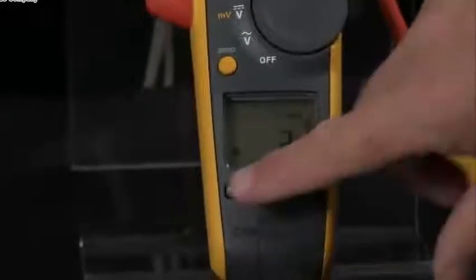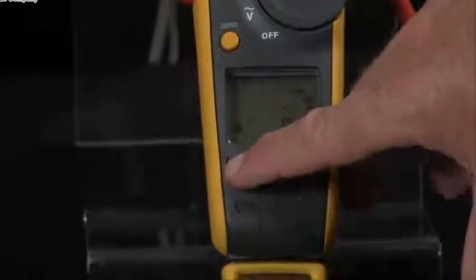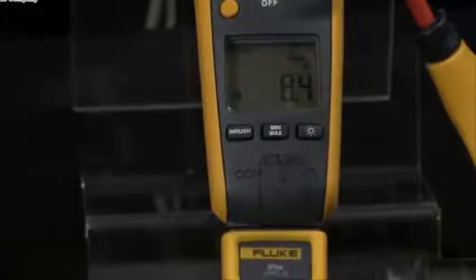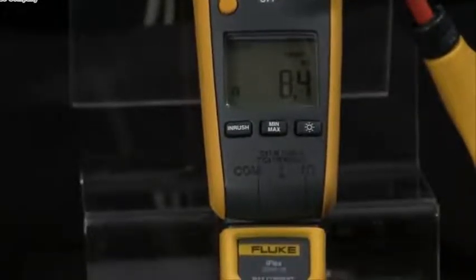To see what the starting or the inrush current is, I press inrush. The meter waits for the motor to start and then it captures my inrush so we can see that we have 8 amps.